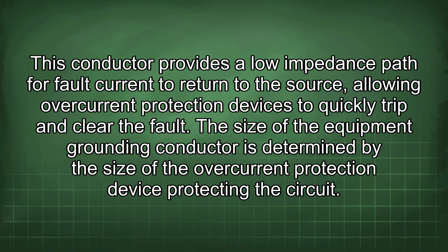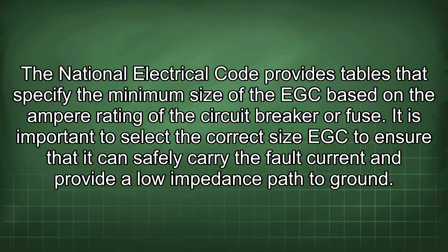The size of the equipment grounding conductor is determined by the size of the overcurrent protection device protecting the circuit. The National Electrical Code provides tables that specify the minimum size of the EGC based on the ampere rating of the circuit breaker or fuse. It is important to select the correct size EGC to ensure that it can safely carry the fault current and provide a low impedance path to ground.